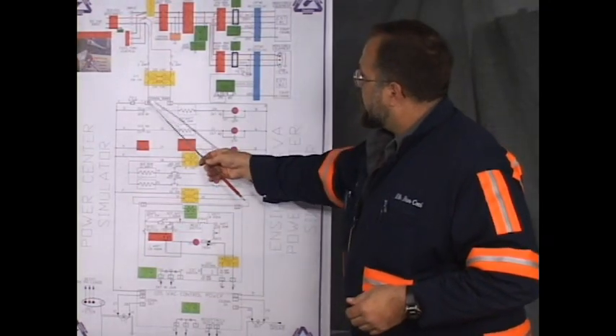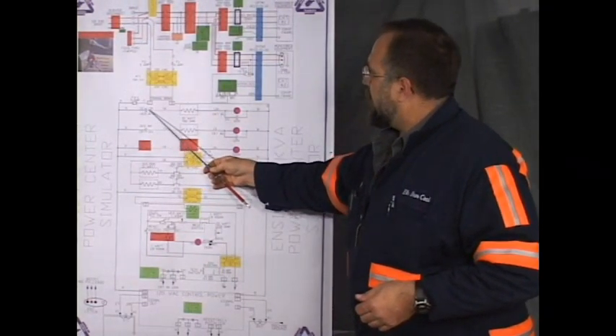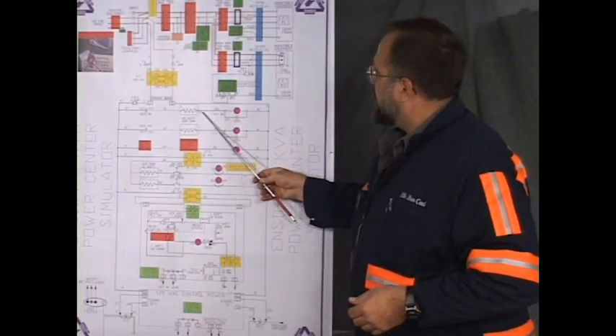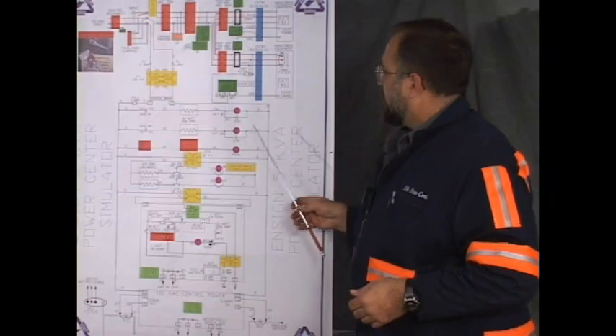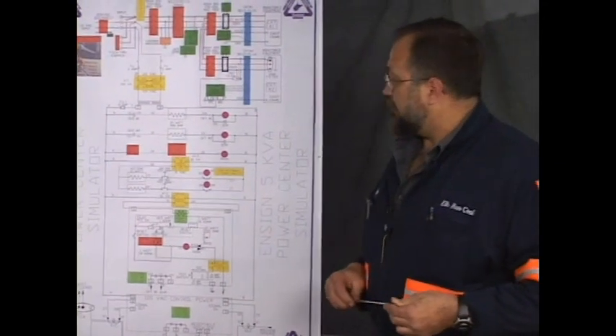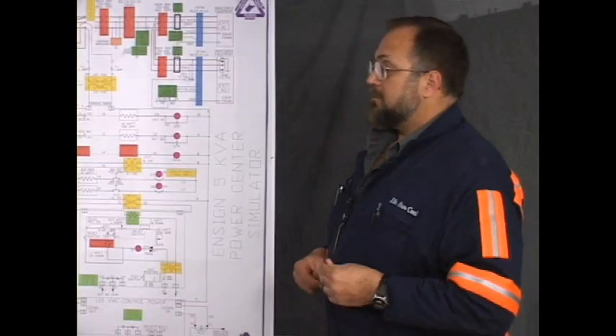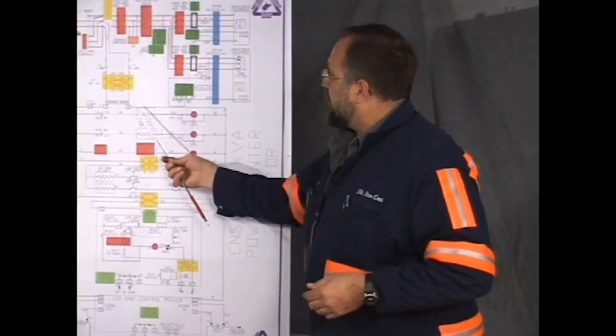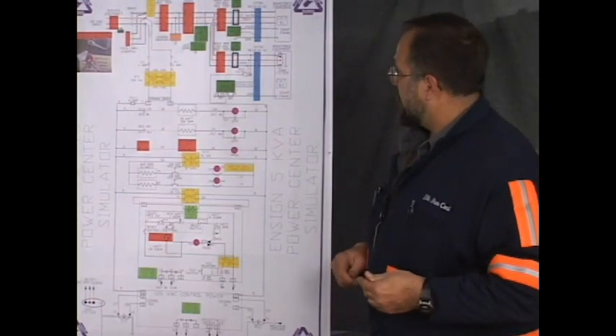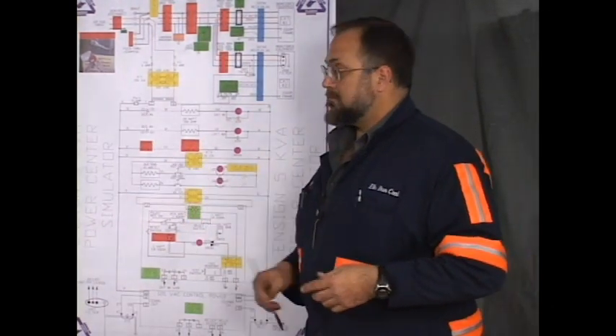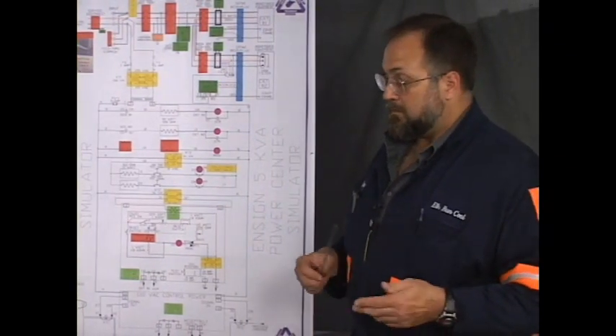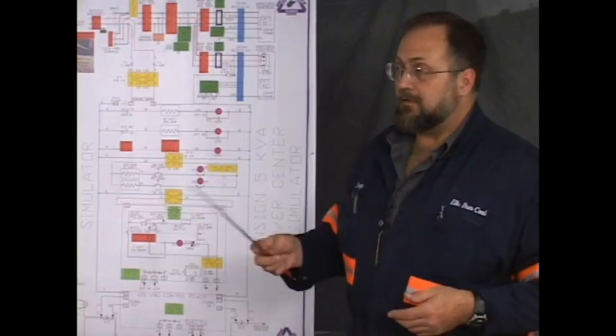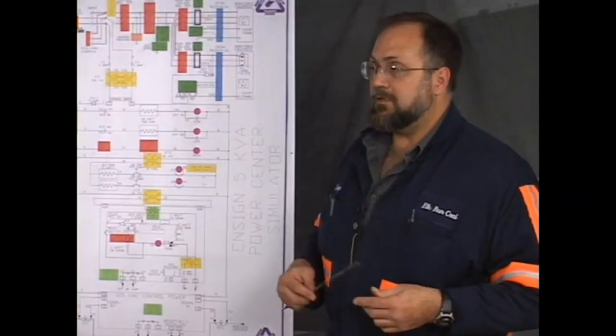When these tips close, it enables power to flow from the line side of the transformer, or the power side, through the circuit to the UVR. When the UVR is energized, the pickup that they refer to is a literal pickup. There's a coil that, when energized, becomes a magnet, actually lifts a linkage off of a trip mechanism in the breaker and allows that breaker to set. And it has to have a return back to the source. Now, the problem states that GCS1 won't pick up, won't close. The problem is probably not in the system, not in the power center. The problem is probably in the machine. And that's what we're going to check now.